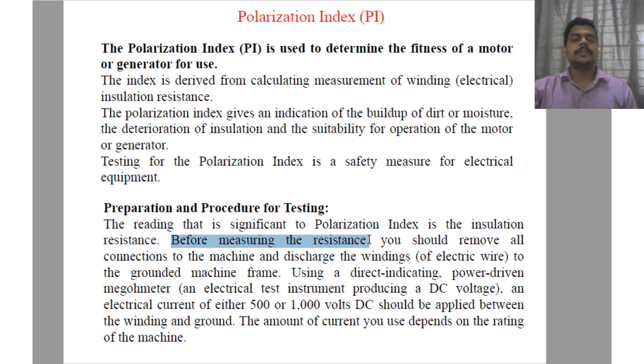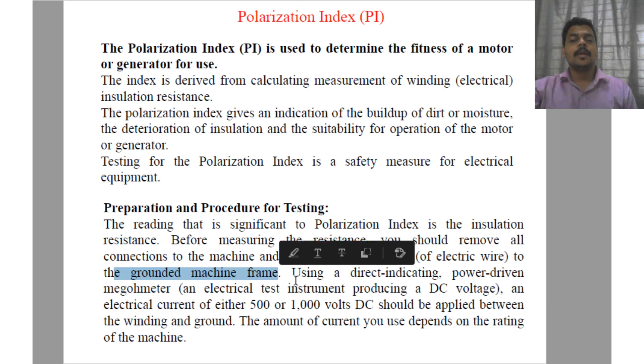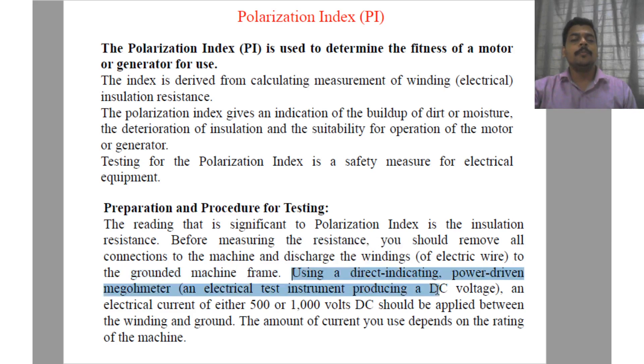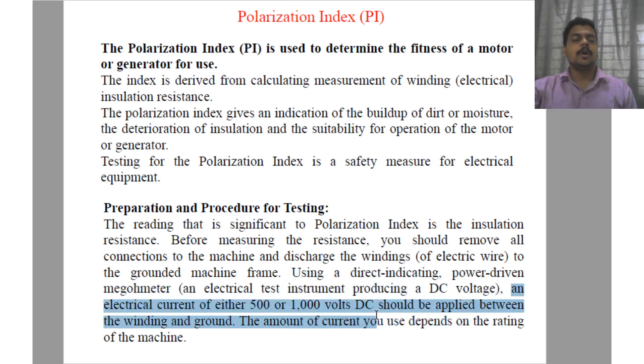Before measuring the resistance, you should remove all connections of the machine and discharge the windings to the grounded machine frame. This is done by using a direct-indicating, power-driven mega-ohm meter, which is an electrical test instrument producing a DC voltage. An electrical current of either 500 or 1000 volts DC should be applied between the winding and the ground.